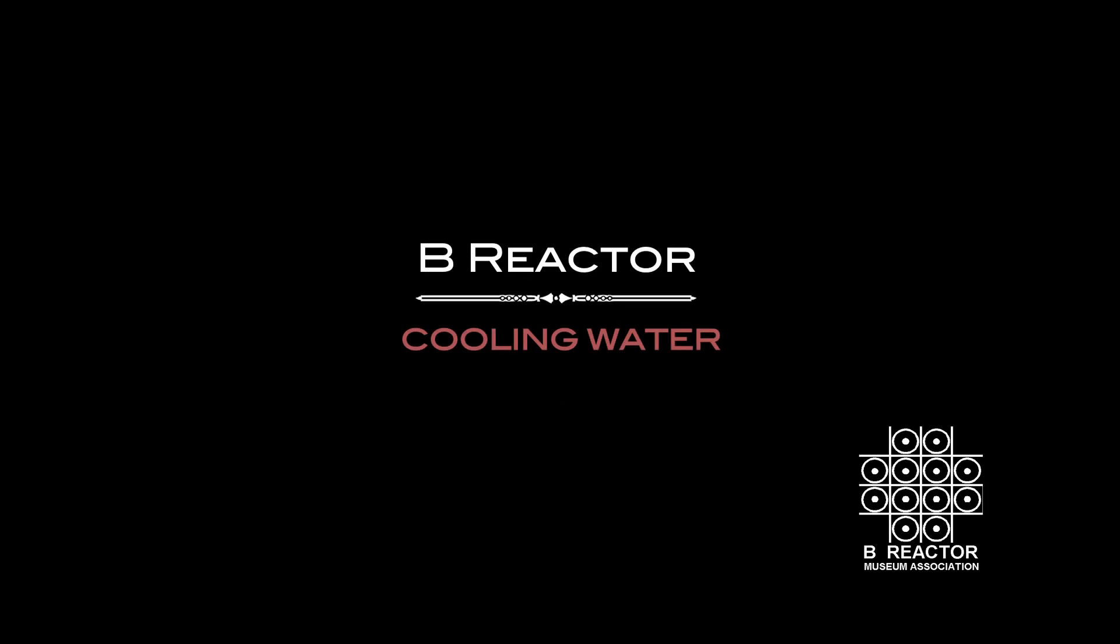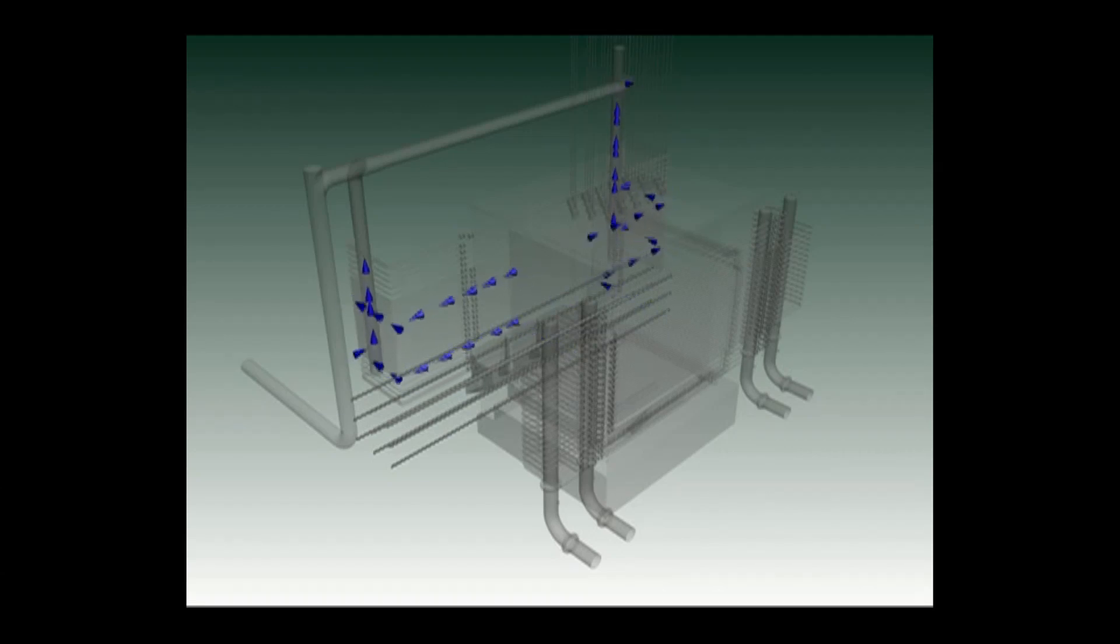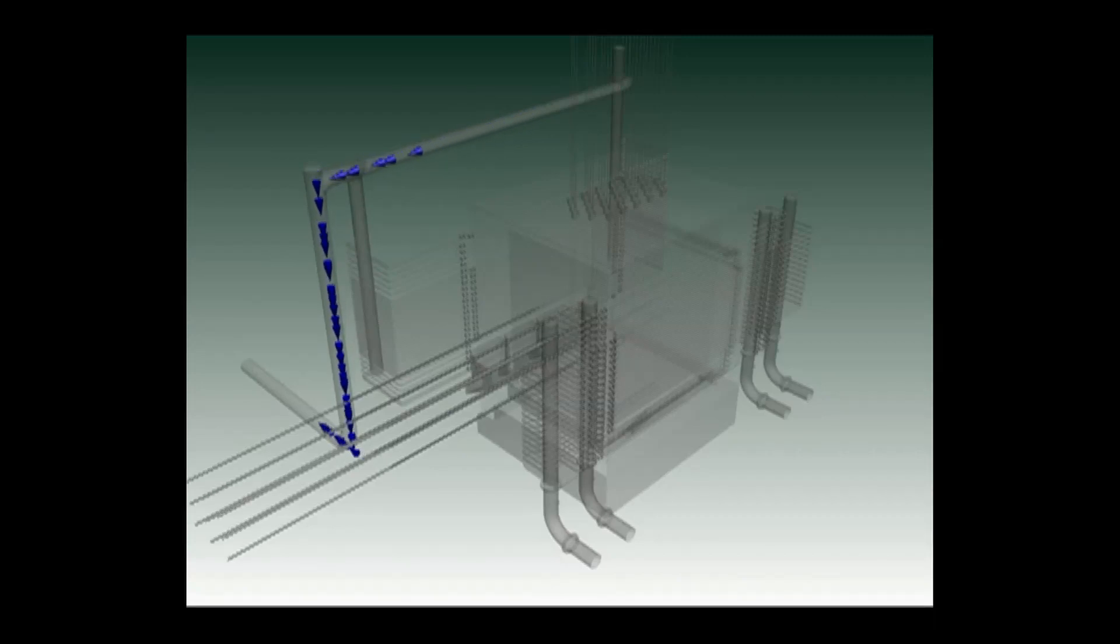Cooling Water. The cooling water for the reactor is piped from the pump house building just outside the reactor building. The 30,000 gallons per minute of treated Columbia River water reaches the reactor through two 20 inch diameter pipes on each side of the front face.